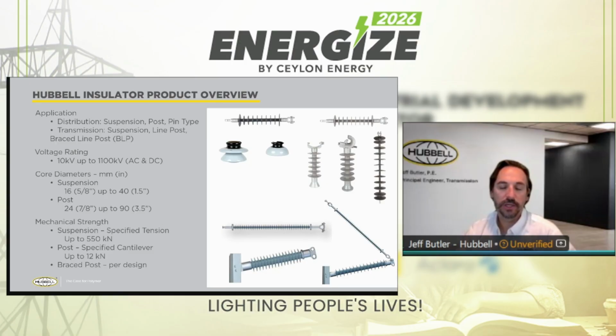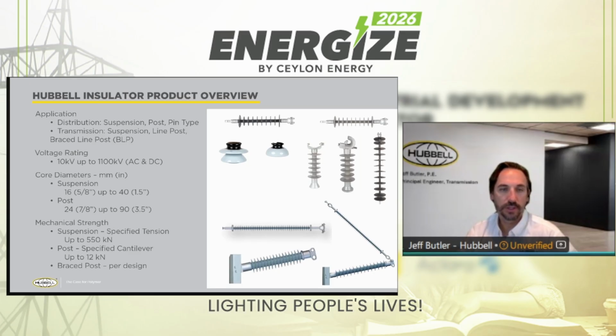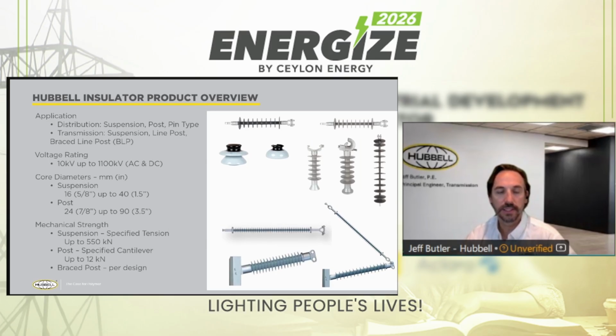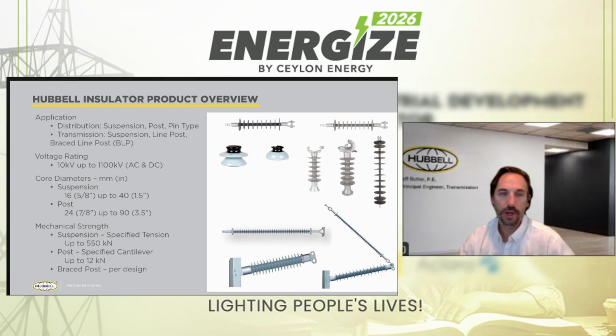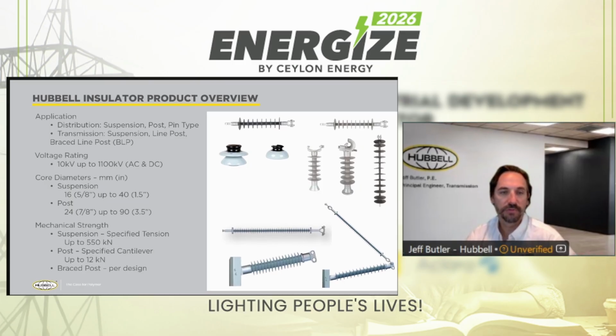I've talked a lot about our history, talked a lot about the importance of polymer insulators, the advantages of polymer insulators. So now let's talk about what Hubbell can provide. So we manufacture distribution, substation, transmission, voltage ratings from 10 kV, as I mentioned, up to 1100 kV AC and DC, different core diameters, 16 millimeters up to 40 millimeters for suspension, posts 24 to 90 millimeters. That's a full range of mechanical strength.